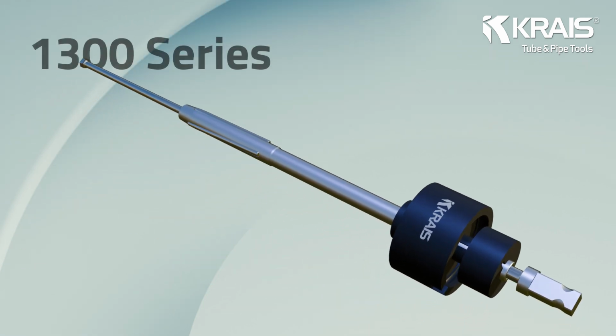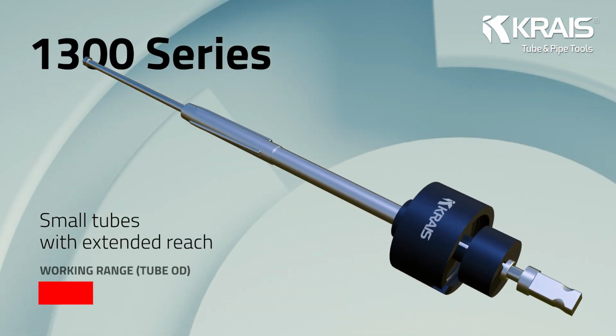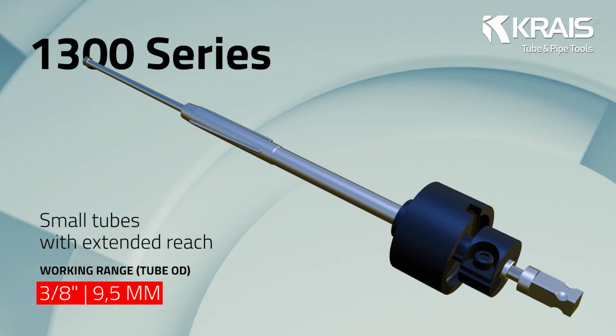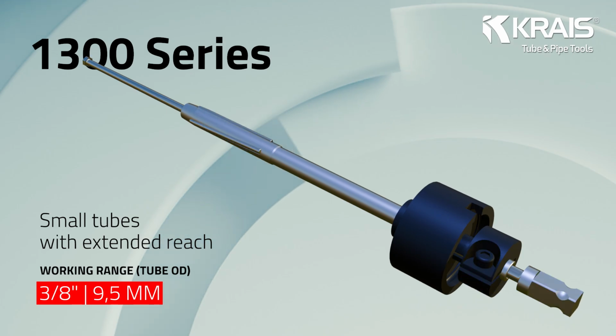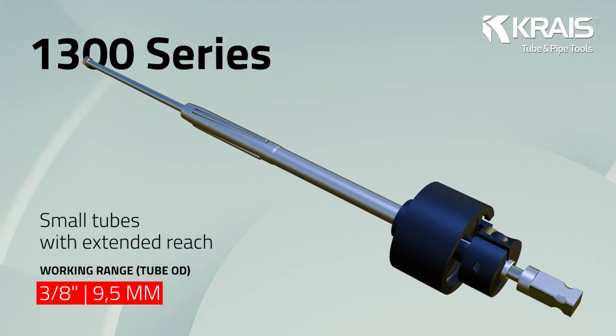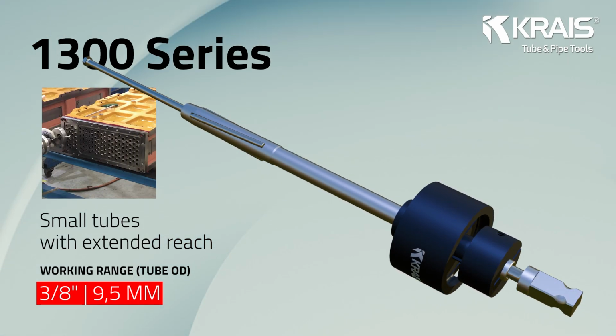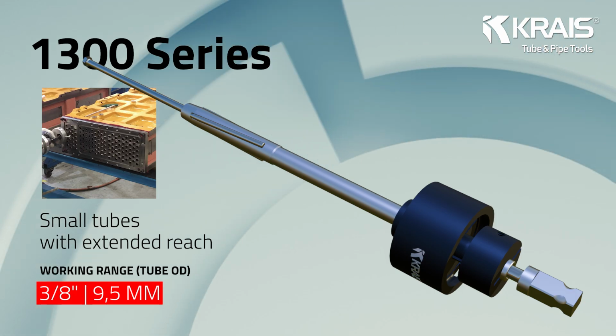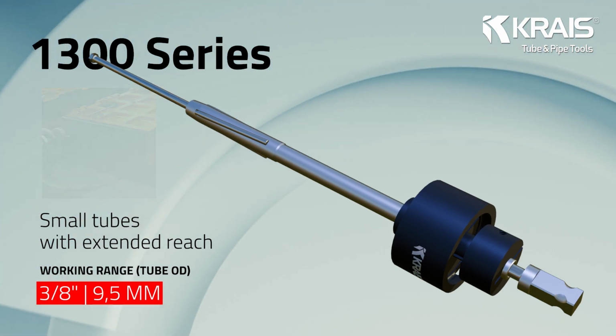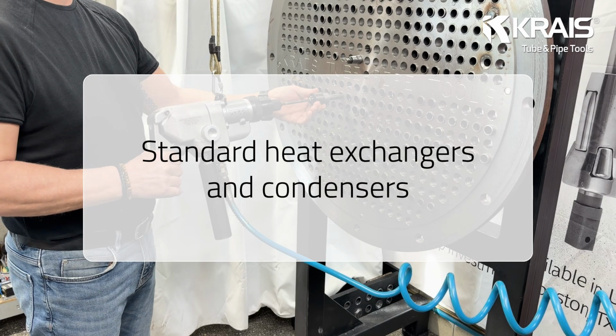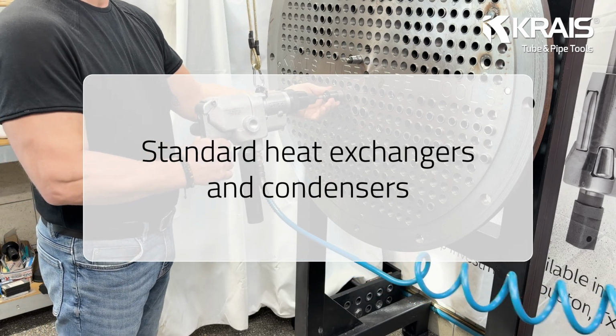KRAIS 1300 series expanders are intended for small tubing where additional reach and a longer roll zone are required, for example with thicker tube sheets or deeper seating geometries. It is a strong choice for small coolers, especially in service and retubing work where access and geometry drive the need for extended reach. Standard heat exchangers and condensers.